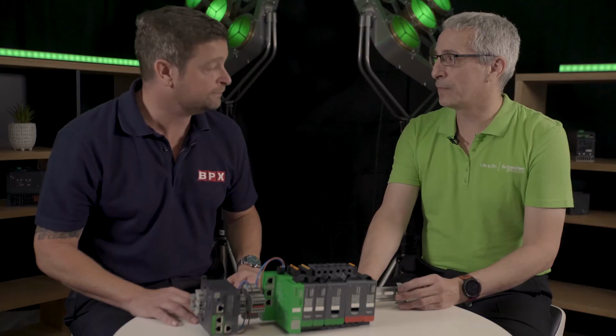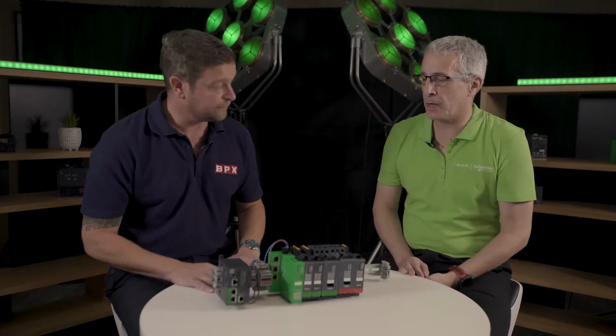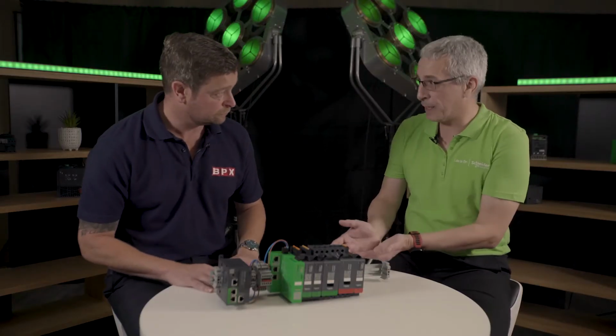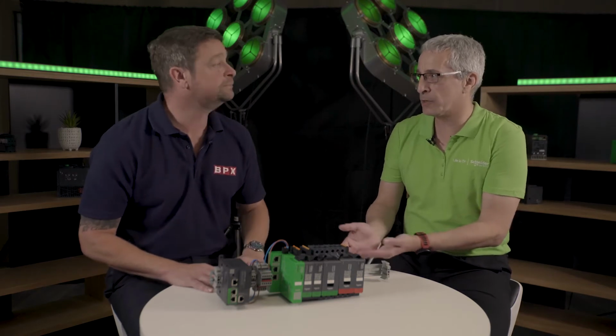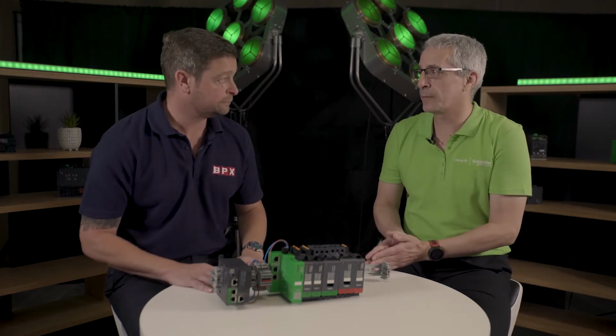So one of the main features about TeSys Island is the reduced design time for implementing a motor control system. One of the concepts that we're using on there is the concept of avatars. The avatars are aimed at fixed speed applications, direct online motors, star deltas, that sort of application. But when you can link a process variable into something like a pump avatar, then you can start to have autonomous control, maybe based on the level in a sump, for example.